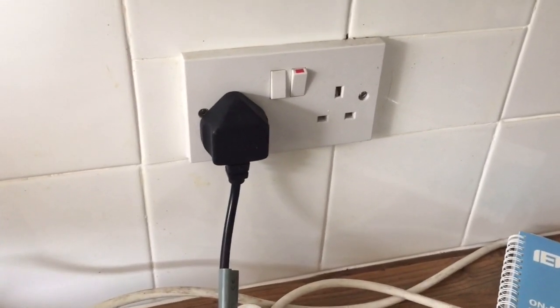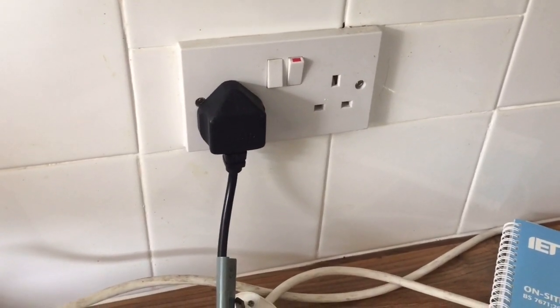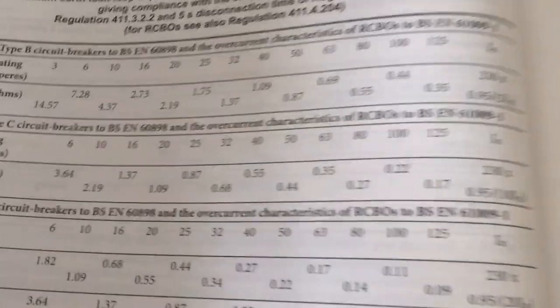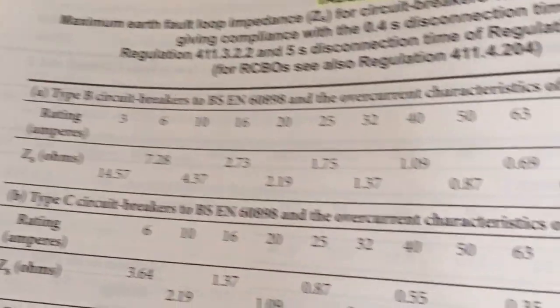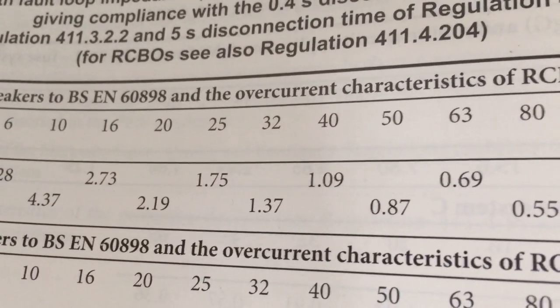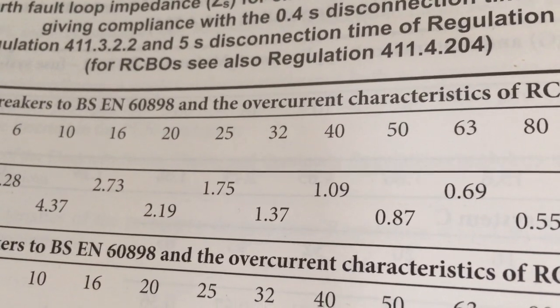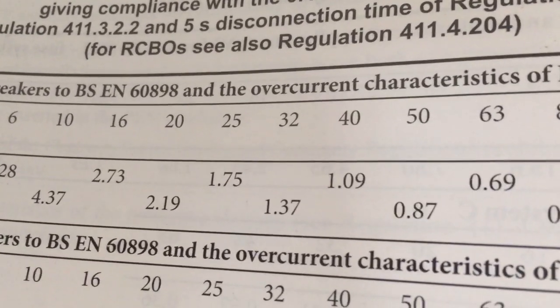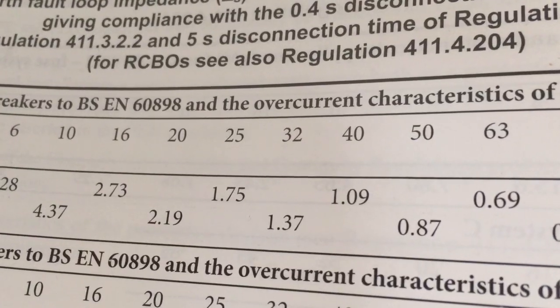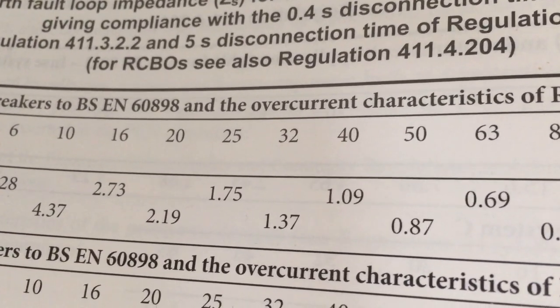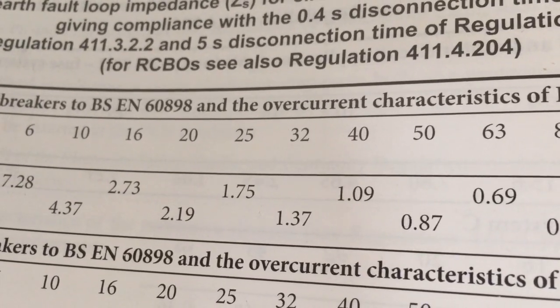I've got the tester plugged into a socket in the kitchen. If we look at expected values and go to the regs, it tells us there for a B-type breaker 32 amp: 1.37Ω, but that is at the conductor operating temperature. Now this is a little thing they like to play on exams — they like to give you the 100% value, because what they want you to do then is to take 80% of that value. It's what's called the rule of thumb for a long time.